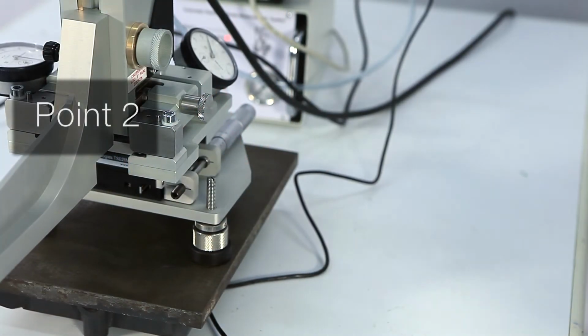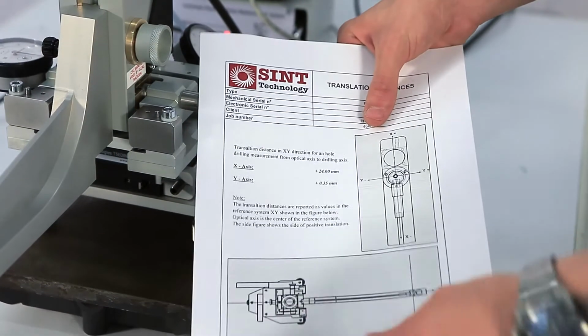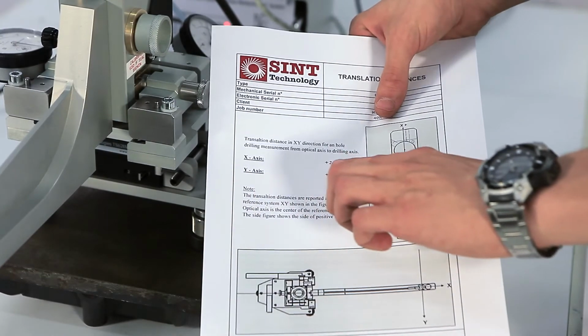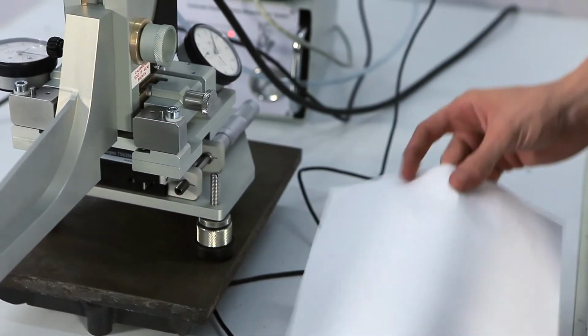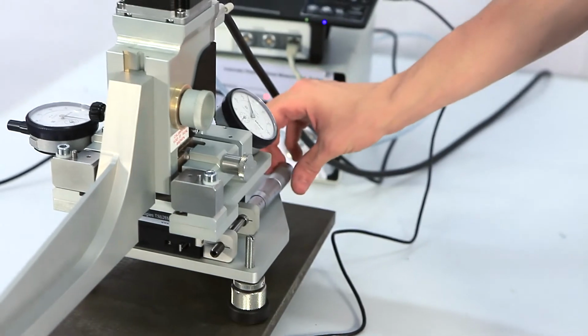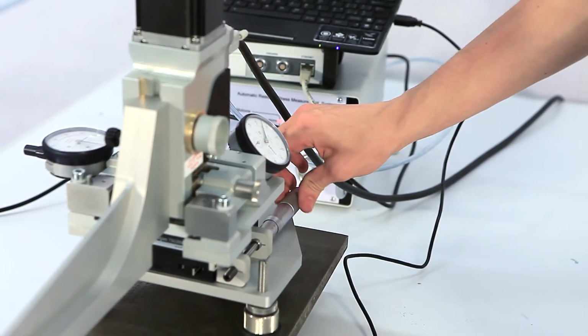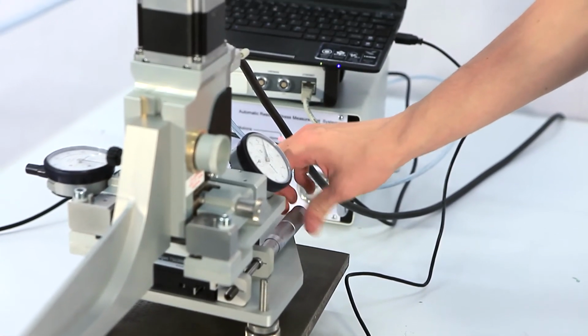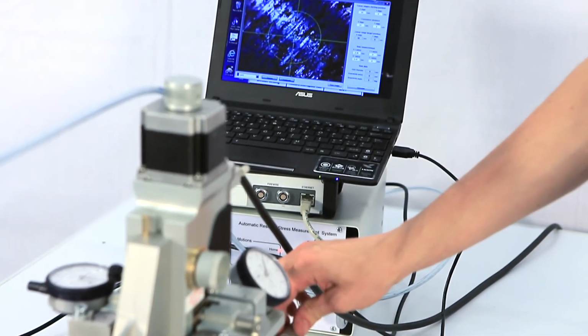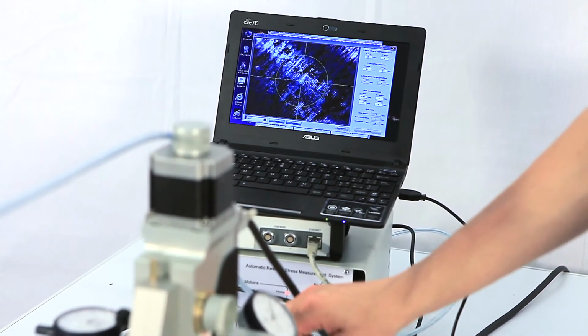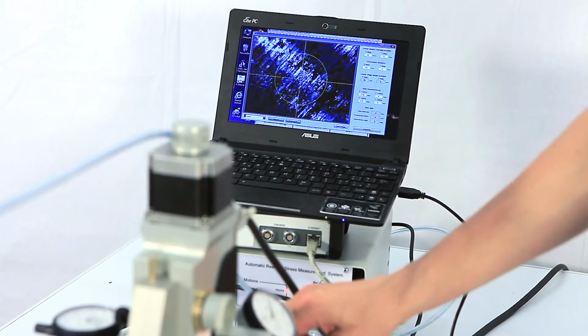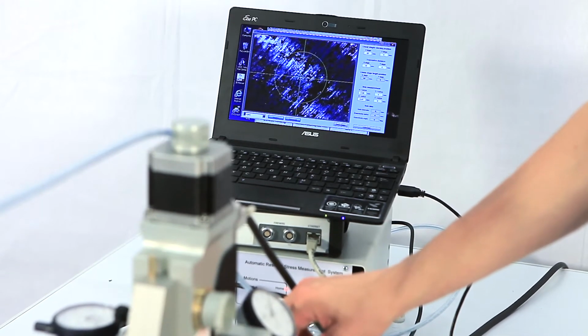Then, move the system in the two directions by using the translation distance written on the calibration certificate. After this operation, verify that these distances are still correct. If not, correct them by referring to the eccentricity values you have obtained.